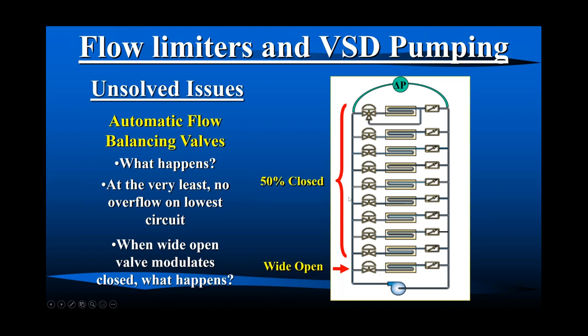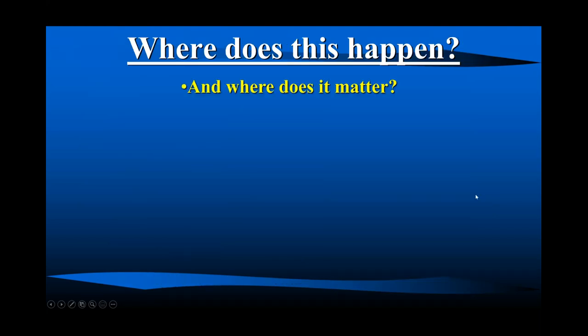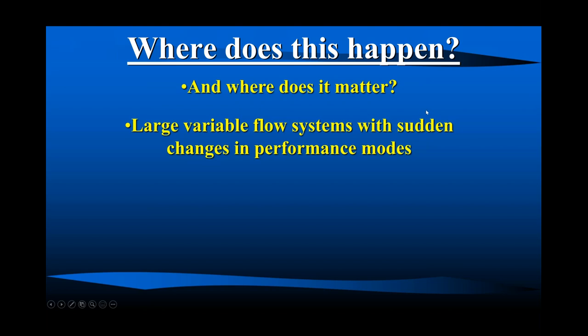And this can be okay in a lot of different applications, but sometimes it's not okay. This temporary change in output as we go further and further from the pump until it winds down can be an issue in certain applications. So where does this happen? And where does it matter? Usually very large systems, and it creates a sudden change in performance. And while it doesn't really matter in apartments or hotels, it matters in hospitals, operating rooms and the like.